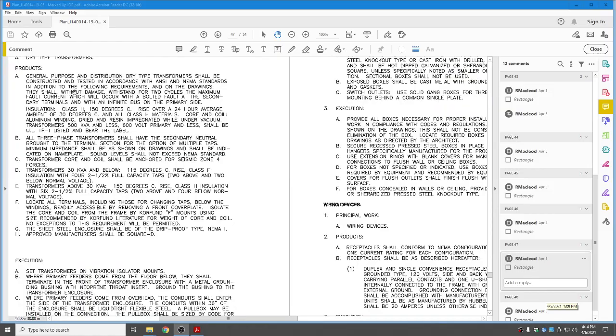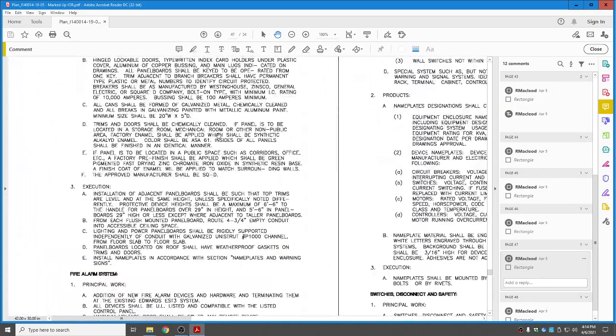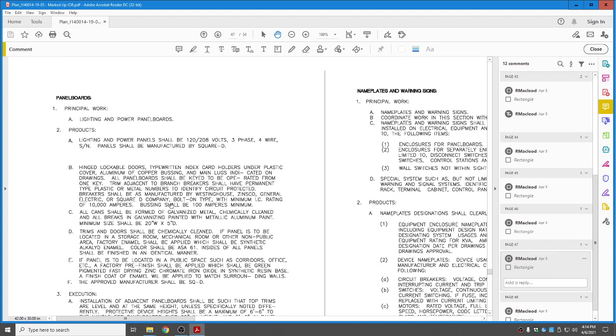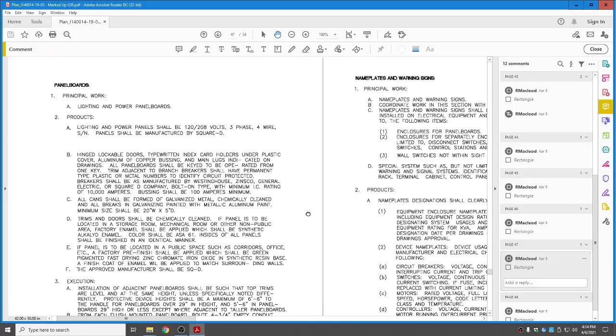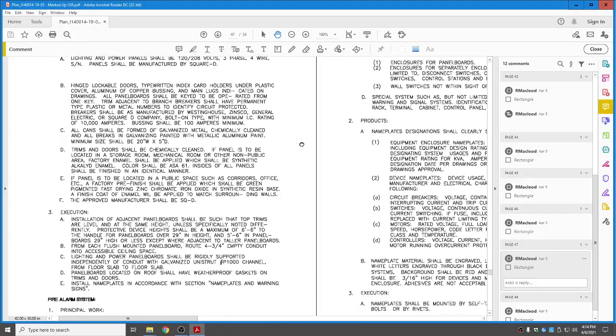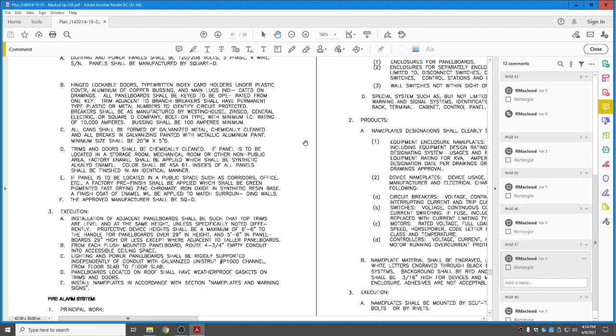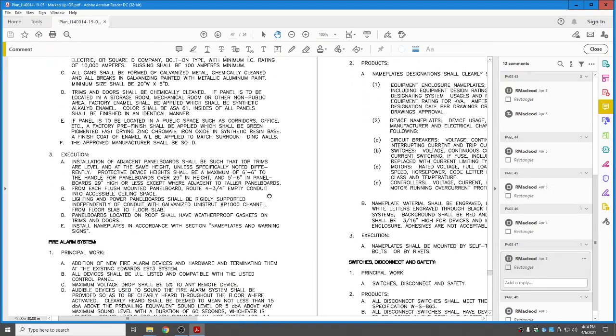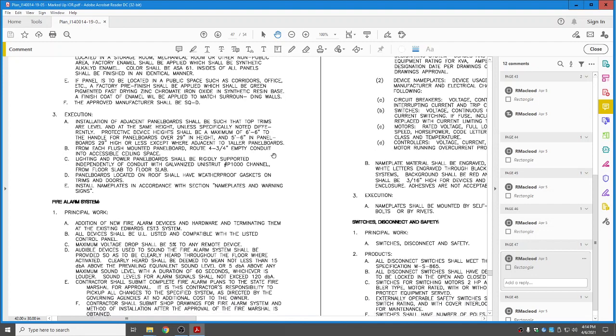Okay, on this page, it's our specifications. Being it's such a small job, they just put the spec items for the electrical right in the electrical section rather than in a separate spec book. Let's zoom in and take a look at some of these. So panel boards give us some idea as to manufacturers of the panel boards, how they get made up, what type of cans to be used. You know, are they rated for exterior or interior exposure, NEMA 1 or NEMA 3R? Basically, instructions for ordering the different panels that the electrical engineer chooses to use.